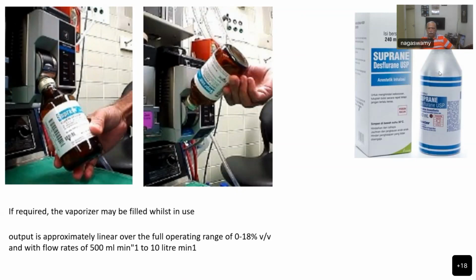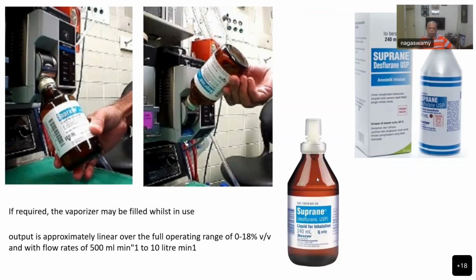And again, last class I told you why this bottle is peculiarly made like this with a plastic coat, because of the high pressure. Earlier it was designed that it may suddenly break when you drop it or when it collides with another bottle. So a glass bottle covered with a plastic coating was the manufacturing method of this desflurane liquid. But the current ones are made of this amber colored bottle because it is photosensitive, and it has the bayonet filling system.